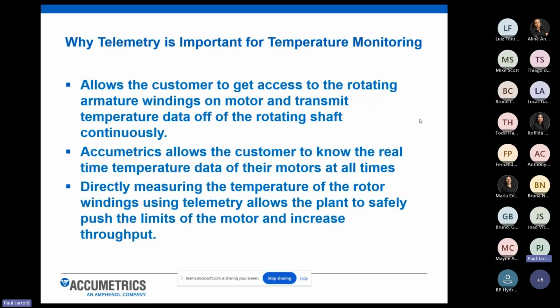There are some systems out there that you can attach to a motor and monitor temperature, but you don't have direct access to them. You have to go in during an outage, pull the device off, plug it into a laptop and say, oh, during this date, we saw we were getting really hot. I wish we knew that in real time. So the advantage of our system is it's a continuous monitoring device that's designed to be mounted to the machine while it's running, and give you that temperature data in real time as the machine is on.